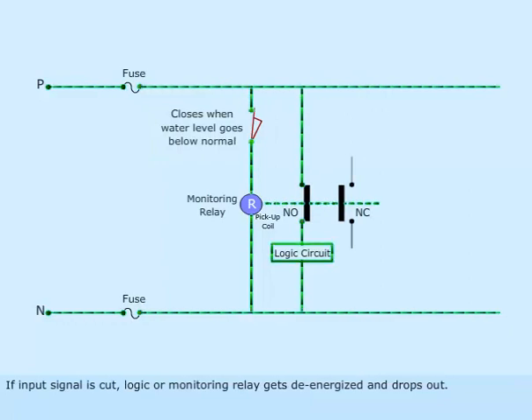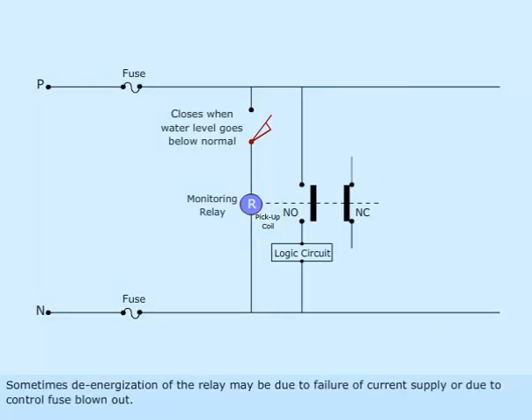If input signal is cut, logic or monitoring relay gets de-energized and drops out. Sometimes, de-energization of the relay may be due to failure of current supply or due to control fuse blown out.